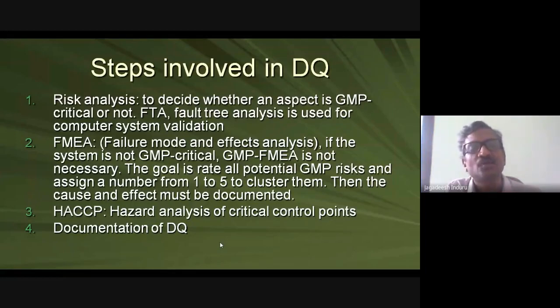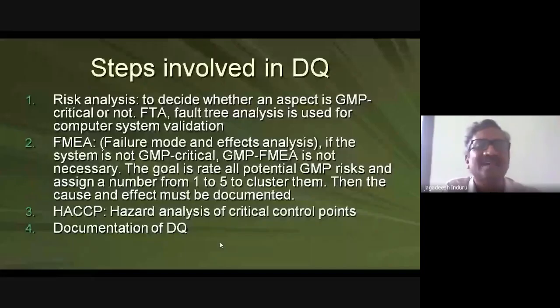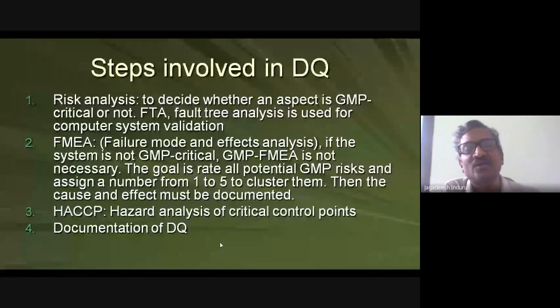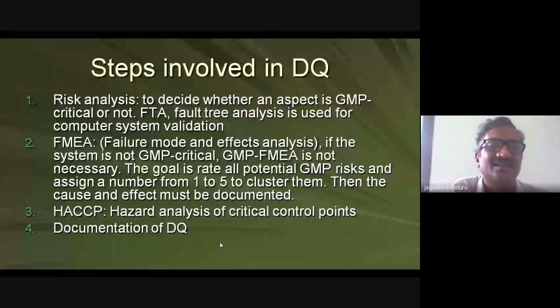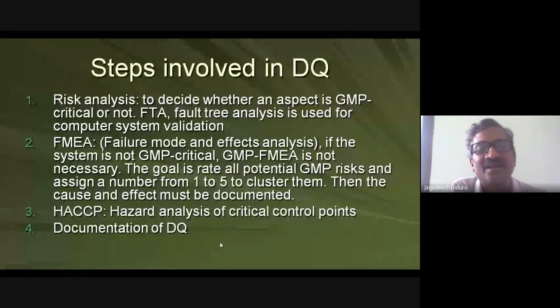The second step is FMEA — Failure Mode and Effect Analysis. If systems are not GMP critical, FMEA is not necessary for them. For faults that are identified as critical in the risk analysis, only those are subjected to FMEA, to reduce unnecessary work. For example, the casing of a mobile phone is not critical to you, but the touch screen performance is — similarly, you focus FMEA on critical equipment parts.